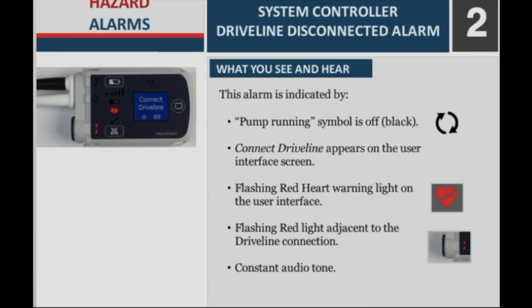System controller driveline disconnected alarm — what you see and hear. This alarm is indicated by: the pump running symbol is off (black); connect driveline appears on the user interface screen; a flashing red heart warning light on the user interface; a flashing red light adjacent to the driveline connection; and a constant audio tone.